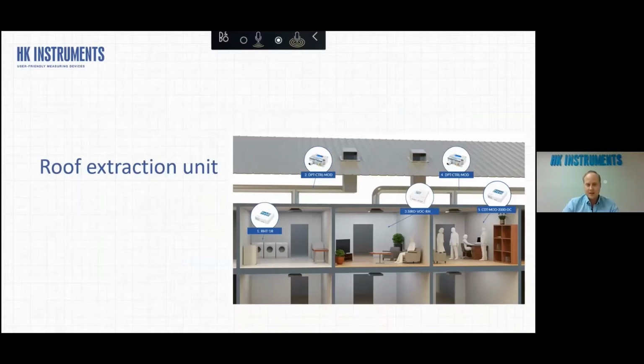So in addition to just measuring the duct static pressure or the airflow rate from the extraction unit fan, it can also control it, as long as the control device is EC fan, which can accept 0 to 10 volt input. So if you're using EC fan, you can measure and control with the same unit, so you don't need to have a separate VFD, which saves costs. And by connecting the relay to DPT control, you can switch between 2 different set points. So for example, you can boost the fan when the humidity levels go over the threshold value. And also you can control based on CO2 from the rooms or VOC now for this new upcoming Zero product.